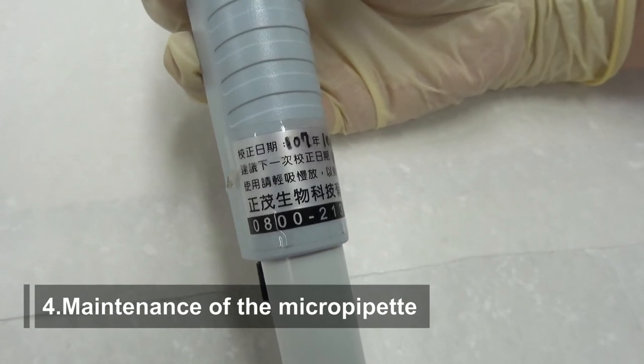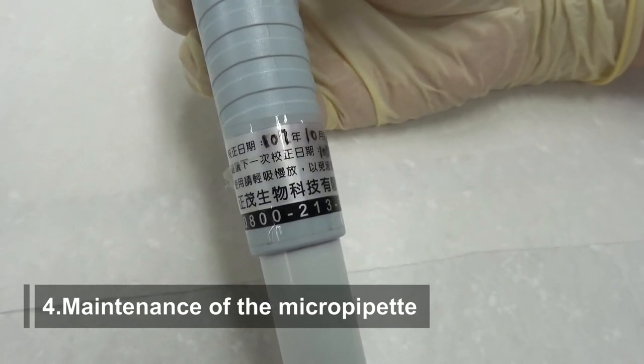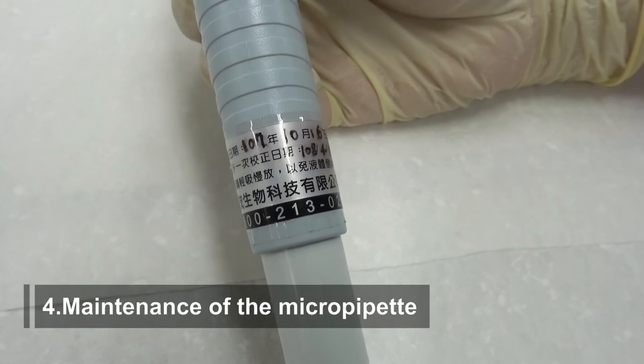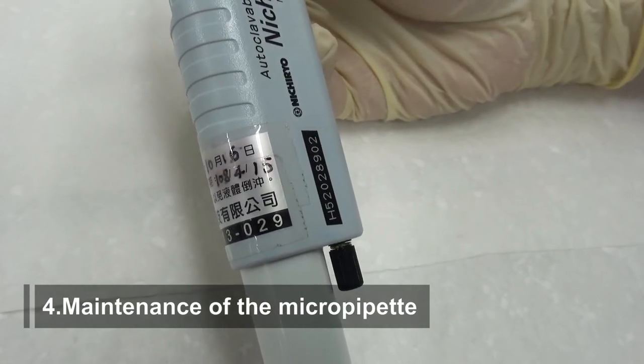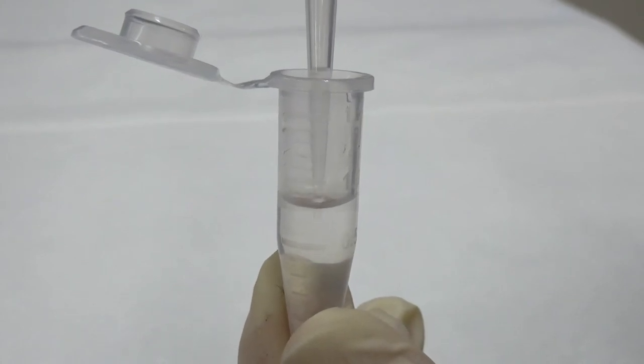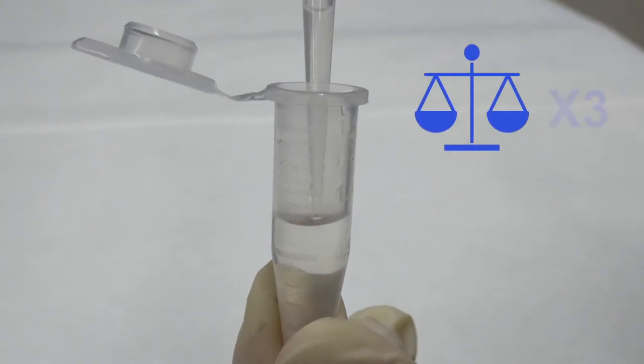Maintenance of the micropipette: The micropipette needs to be calibrated regularly to ensure accuracy and improve experiment reproducibility. A simple approach to check accuracy is to aspirate a certain volume of water and measure the weight. Repeat 3 times and calculate the error.